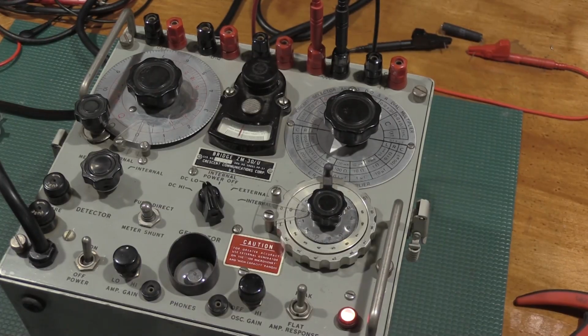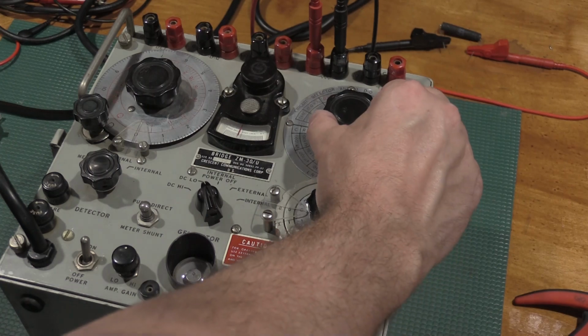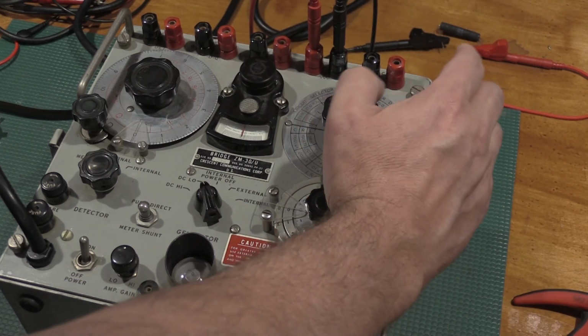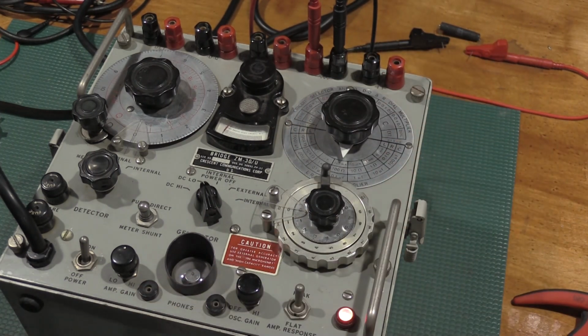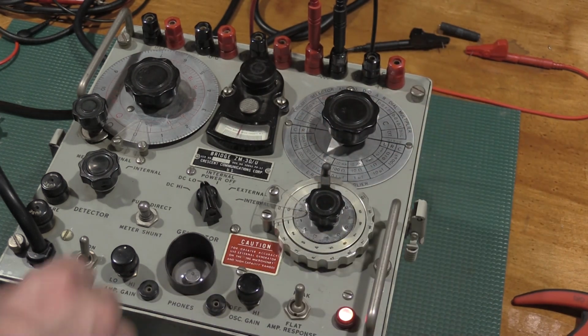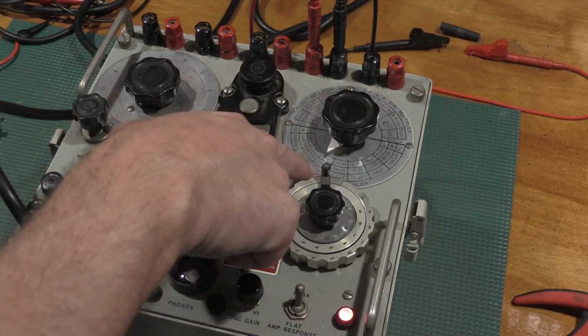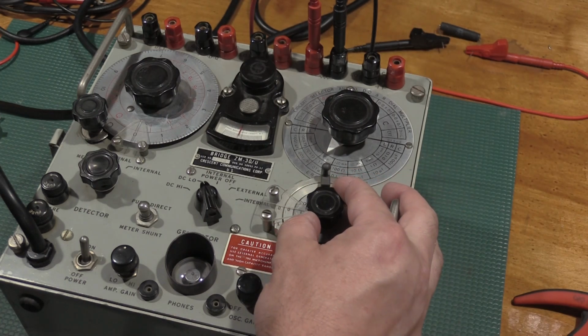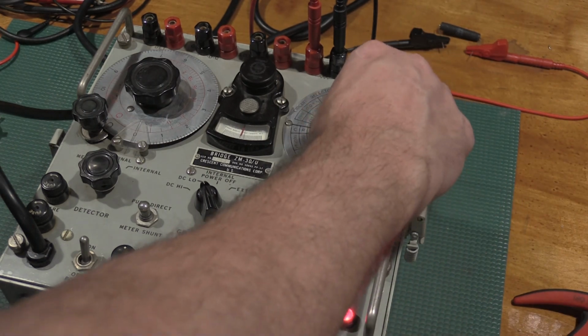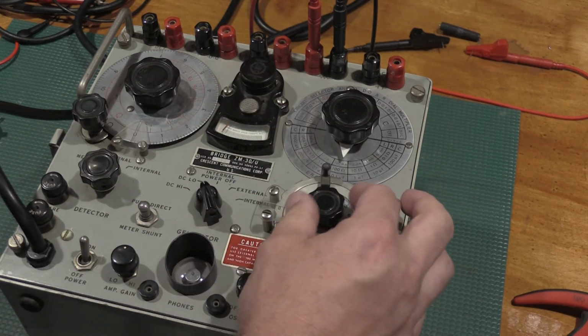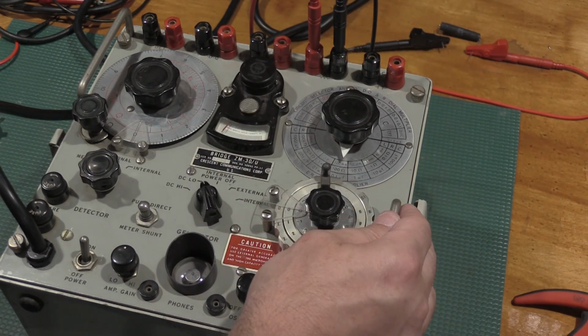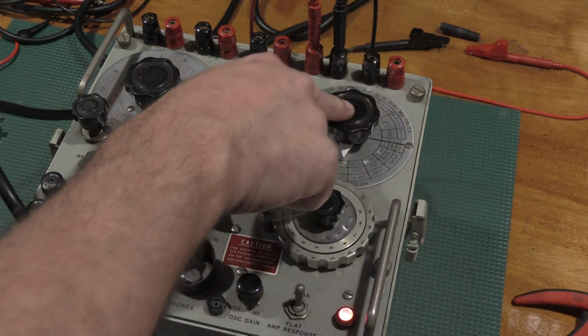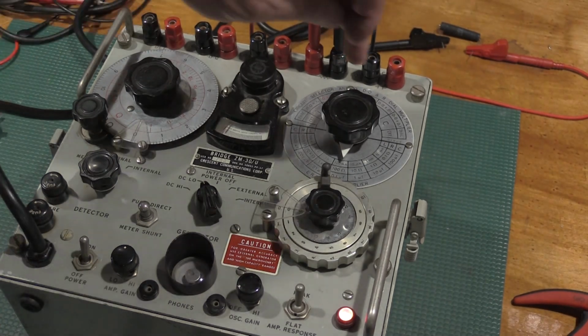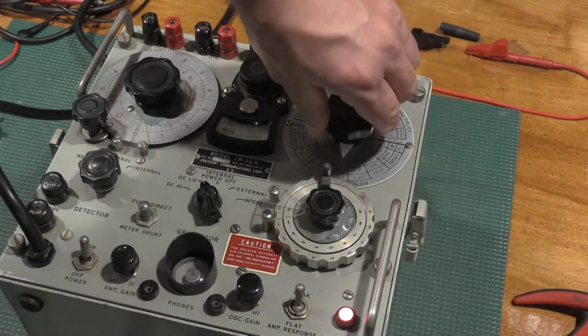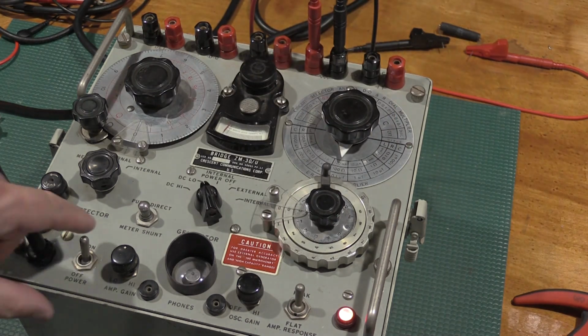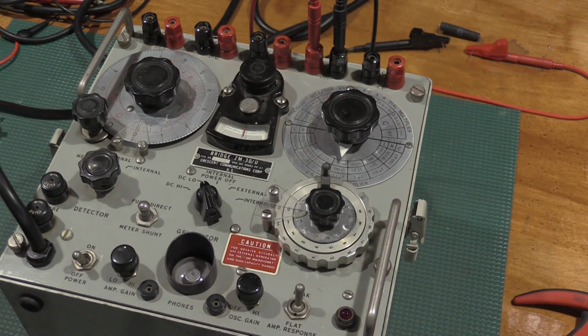Well, the unit was working, and then I moved the range switch. I need to do some cleaning on this range switch. It is not happy because it's saying it's balancing at a kilo ohm, roughly the kilo ohm range. But then if I move it down to the 100 ohm range, it tells me I need to take... So I have a problem in this range switch we got to clean up. So let's see what we can do about that.